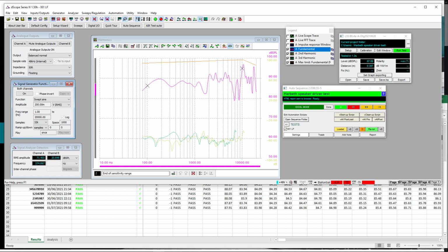These limit lines can be created from a measurement. We can take a result and just shift the result up by a few dB and make that a limit line. We can create them from a script, perhaps calculating some limits or reading from a table. And one example might be to create a table in Excel where we use some statistical analysis to create an n times sigma limit curve.